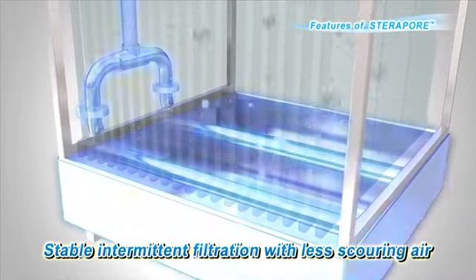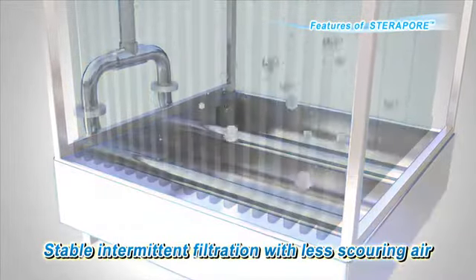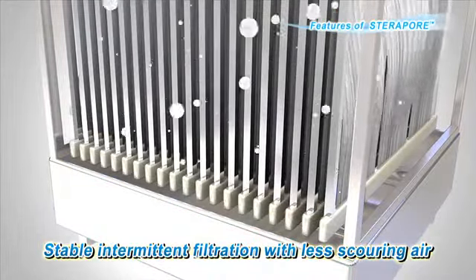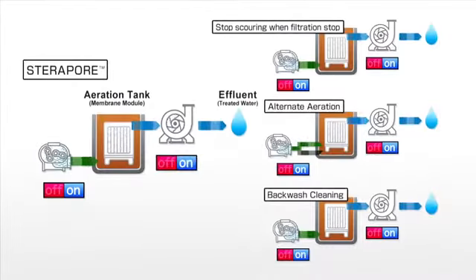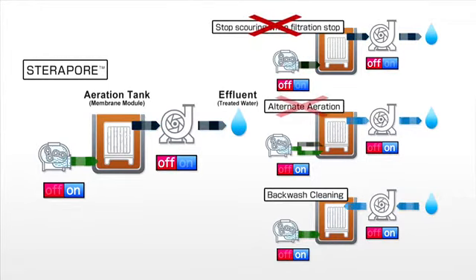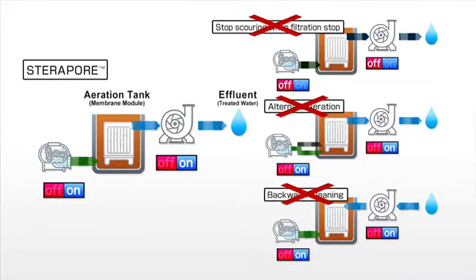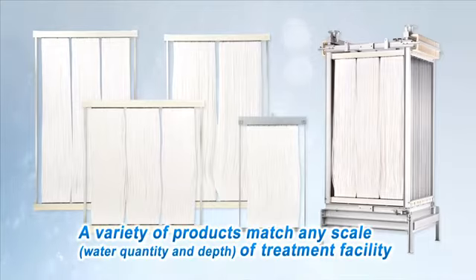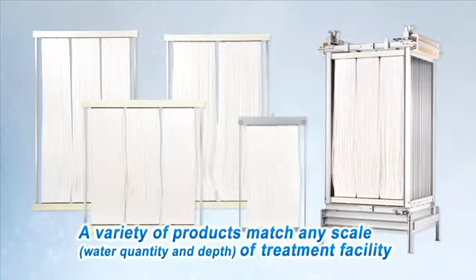Since intermittent filtration in constant low air aeration environments is possible, installation and operation management are simplified. Additional controls and equipment required by other companies — such as controls of aeration during times of filtration stoppages, alternate aeration, and backwash cleaning — are not necessary. STERAPORE offers a variety of elements and modules in accordance with the scale of the treatment facility, accommodating various requirements such as water quantity and water depth.